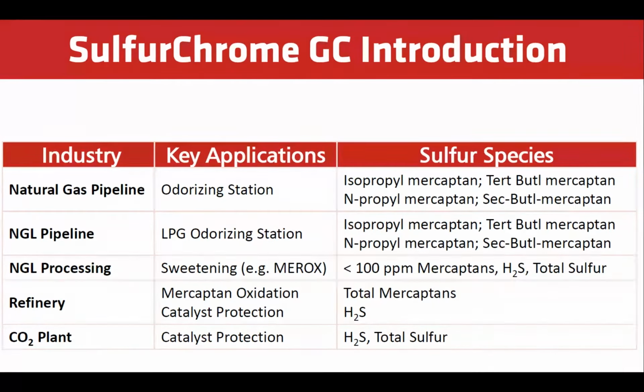For the natural gas liquid processing, sweetening, less than 100 ppm mercaptan, H2S, total sulfur. In the refinery, you have mercaptan oxidation, catalyst protection, and for that you would measure total mercaptans, H2S. CO2 plants, catalyst protection, again, H2S, total sulfur.